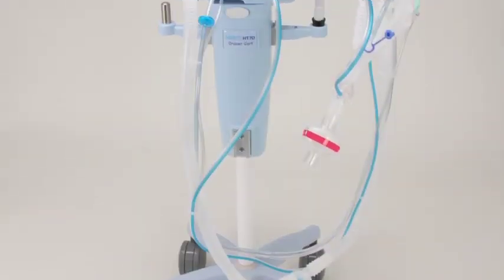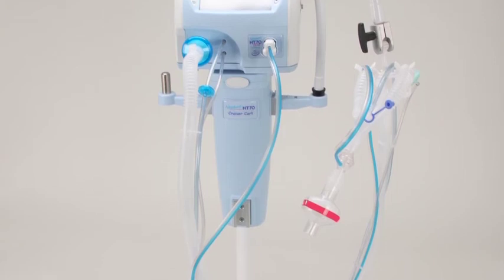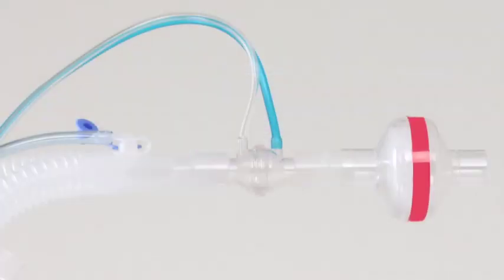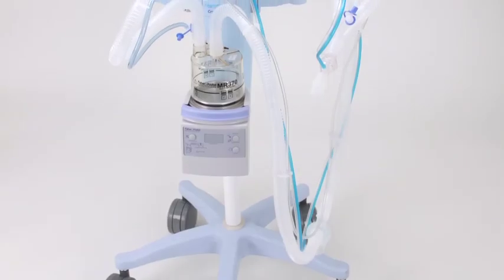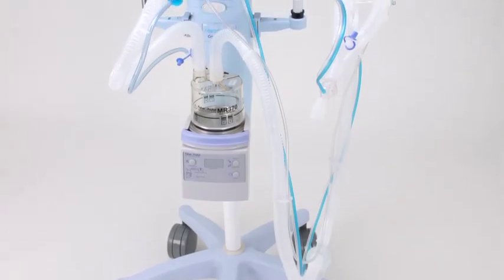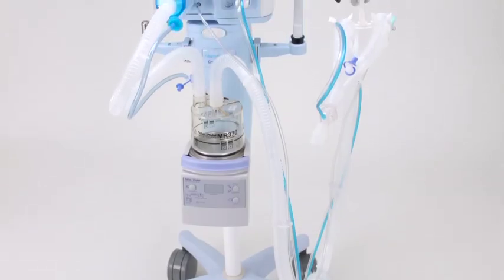When attaching an HME in conjunction with the on-airway flow sensor, you will attach the sensor to the Y connector of the circuit, then connect the HME to the patient side of the flow sensor. In this case, since you will use the exhaled volume alarm to detect disconnect, there is no reason to move the pressure line.